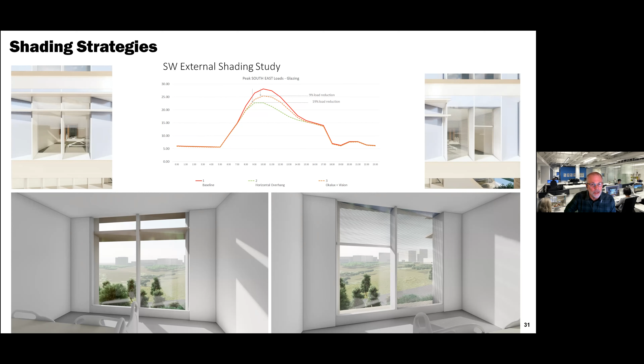It's a combination of the technology of the glass in the lower right-hand corner. We worked our way towards a glass that had a visible light transmittance of almost 50% and a solar heat gain coefficient of 0.23. That became kind of our starting place as we worked our way up and down what you could afford, what would give the best results. And then began introducing shading devices at different heights, whether at a 12-foot height, a 9-foot height, a depth of anything from 0 to 6 feet. And what we found is that the highest utility of shading device really occurred within the first 2 to 3 feet of that device. And it certainly was benefited by its location on that opening.